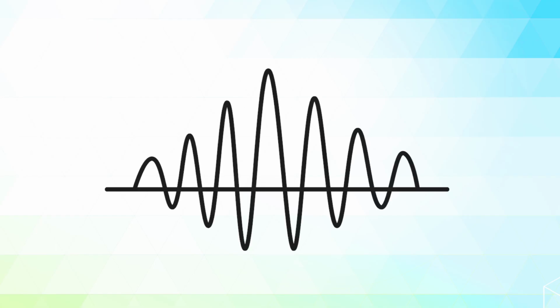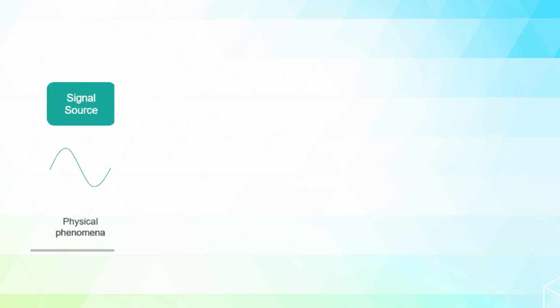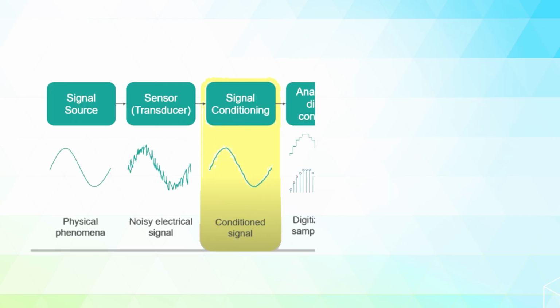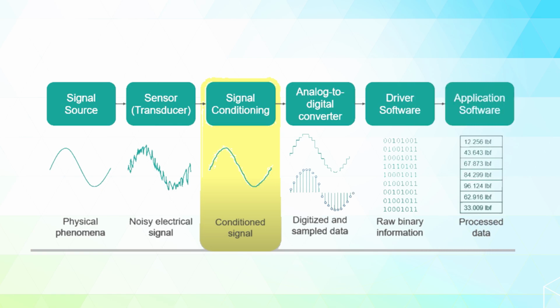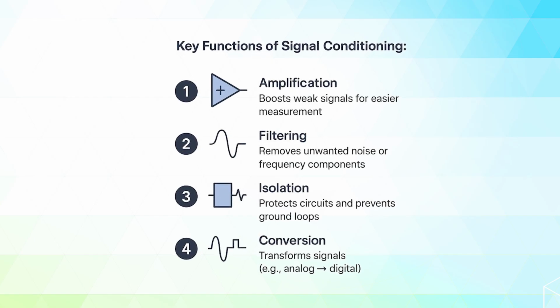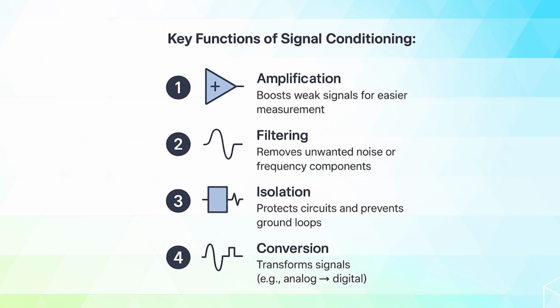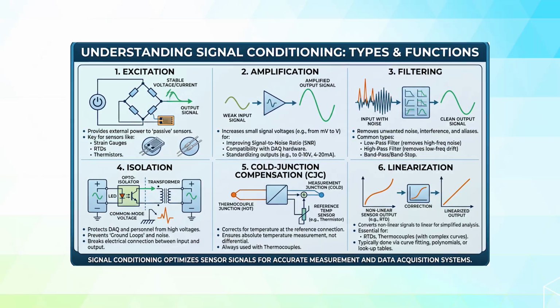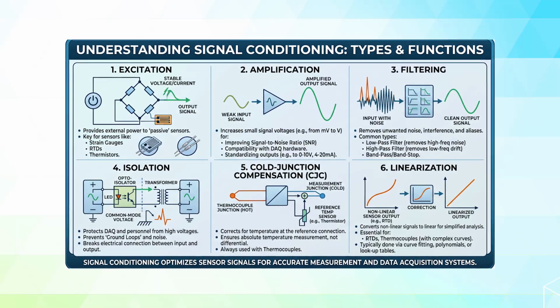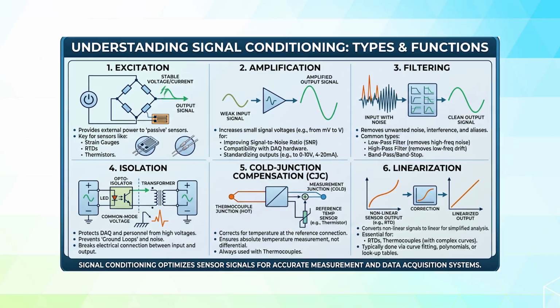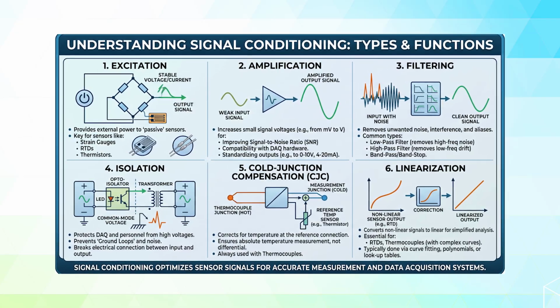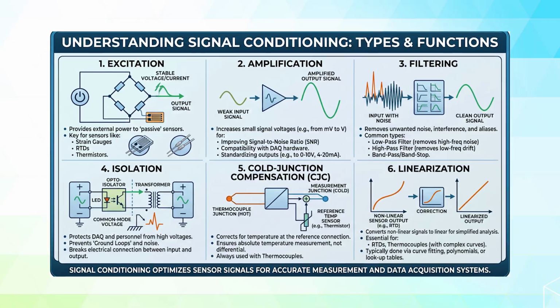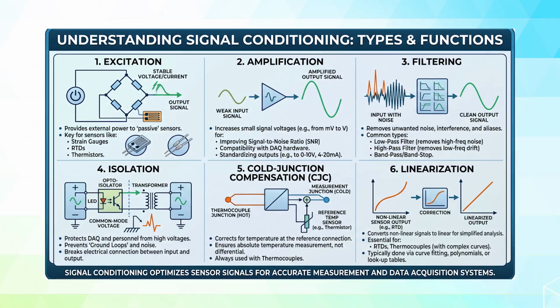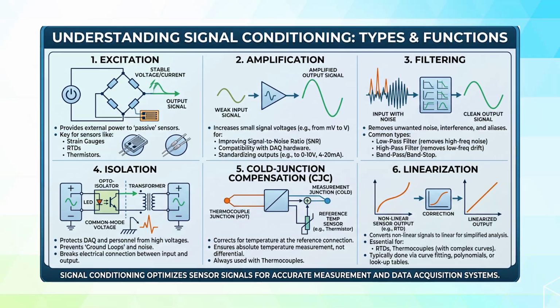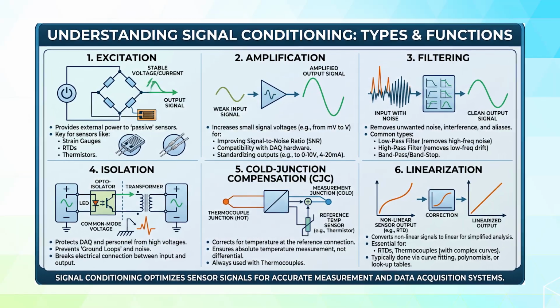Then there is signal conditioning. Many sensors do not produce signals that are ready to measure directly. Thermocouples, RTDs, strain gauges, accelerometers, microphones, and bridge sensors often require some form of conditioning before the data is useful. This may include excitation, amplification, filtering, isolation, cold junction compensation, or linearization. This is why measurement-specific modules are so useful in platforms like CompactDAQ, CompactRIO, and PXI. The right module does more than capture a signal. It prepares that signal for accurate measurement.